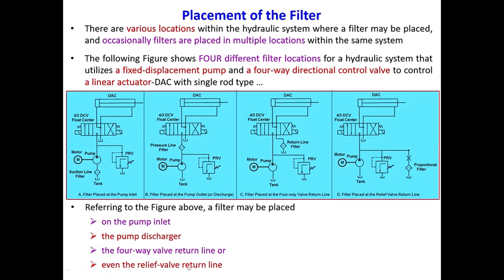here the filter is placed. Schematic A shows a hydraulic system where the filter is located at the pump inlet. Already we know that the reservoir is frequently equipped with a strainer in this location, and the difference between the strainer and the filter is not precise. Often a strainer is simply viewed as a coarse filter. One advantage of putting a filter at the pump inlet is that the pump is one of the most expensive components in the system, and pre-filtering the fluid that enters the pump will reduce the chances of pump failure. It is also true that if the pump begins to experience adverse wear due to contamination, by its very nature, the pump will distribute these newly created wear particles throughout the rest of the system, thus enhancing the chance of downstream contamination.